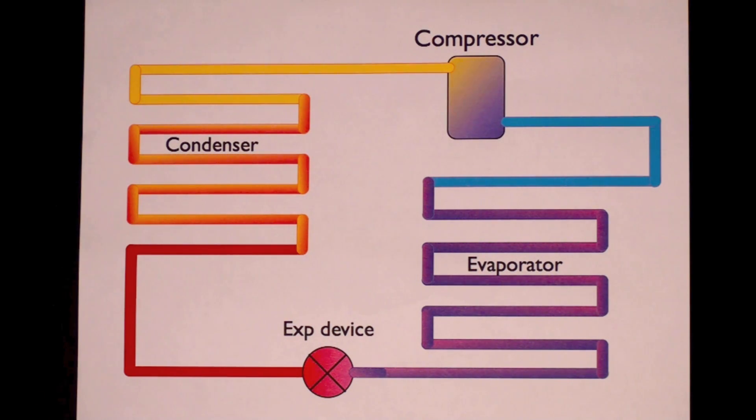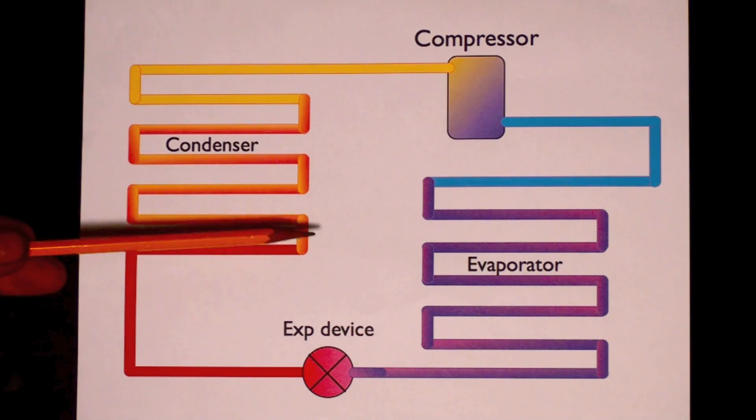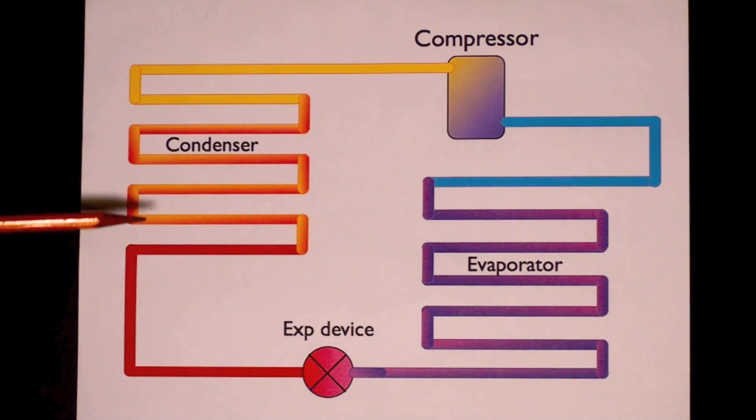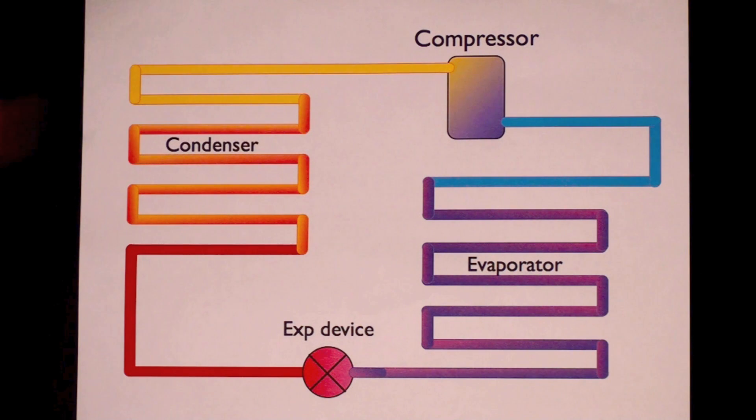Now when it becomes all liquid, remember up here we were a saturated mix. So there was gas and liquid refrigerant and it was condensing. So it's going to condense at the same temperature. Down here it's all liquid and so it will subcool. That means it's going to get cooler than the condensing temperature.